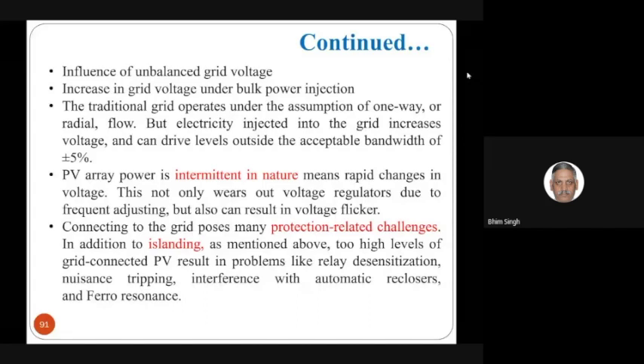Another is the influence of unbalanced grid voltage, and the increase in grid voltage under bulk power injection. The traditional grid operates under the assumption of one-way radial flow, but electricity injected into the grid increases the voltage and can drive levels outside the acceptable bandwidth of ±5%. And PV power is intermittent in nature, meaning rapid changes in the voltage. This not only wears out voltage regulators due to frequent adjusting, but can also result in voltage flicker, and connecting to the grid brings many protection-related challenges. In addition to islanding, as mentioned above, too high a level of grid-connected PV results in problems like relay desensitization, nuisance tripping, interference with automatic reclosure, and Ferro resonance.